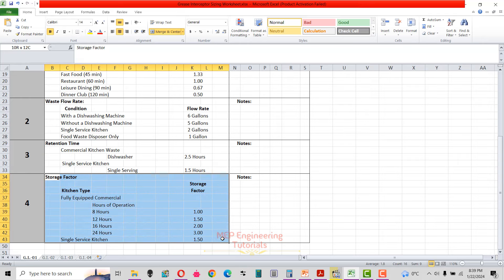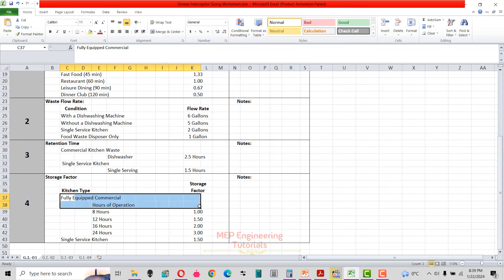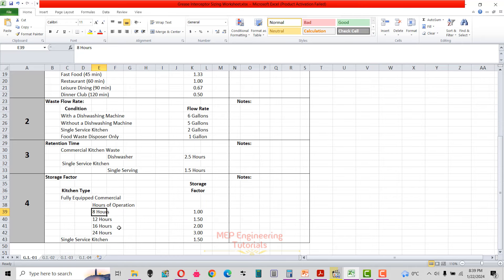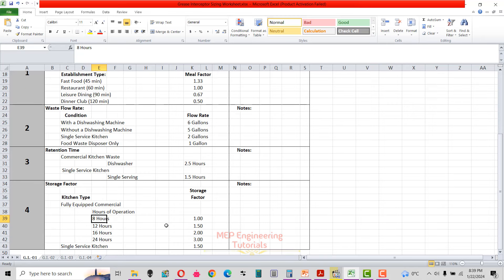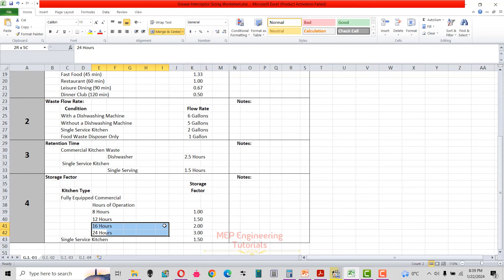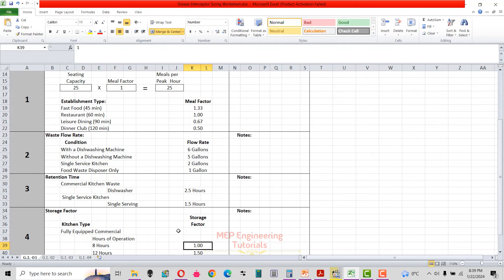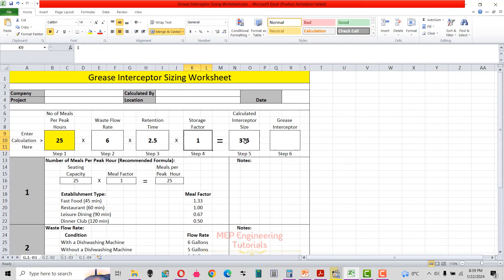Step 4: get the storage factor. As per the Uniform Plumbing Code, for a fully equipped commercial kitchen the storage factor depends on hours of operation — 8 hours: 1.0; 12 hours: 1.5; 16 hours: 2.0; 24 hours: 3.0. Since our kitchen operates 8 hours, the storage factor is 1.0. After entering all values, we calculate the interceptor size, which comes out to 375 gallons.